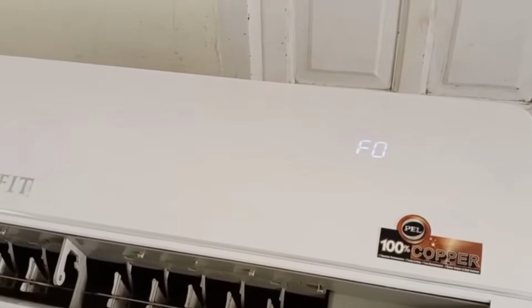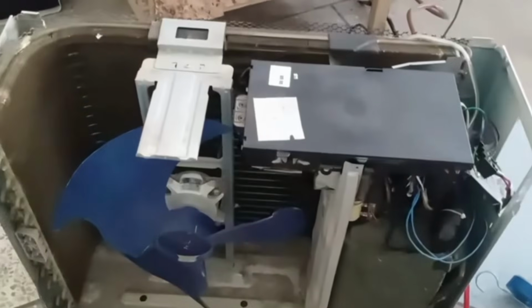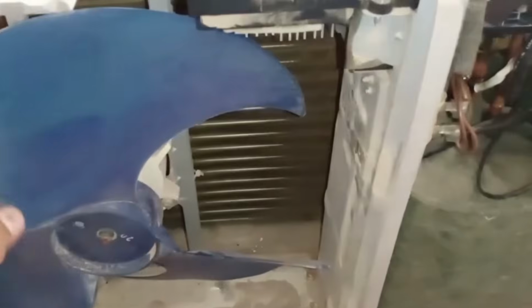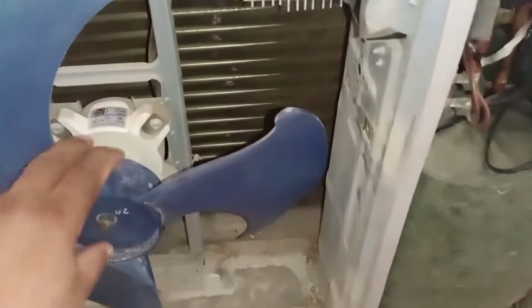This is an issue related to the outdoor unit, so let's move to the outdoor unit and see why this error code appears. Now we have moved to the outdoor unit. Look here. When the outdoor fan motor stops working for any reason, the F0 error code will appear on the display. If the fan motor gets jammed, the same error will occur. Similarly, if the supply from the PCB to the fan motor doesn't reach it, the error will also appear.